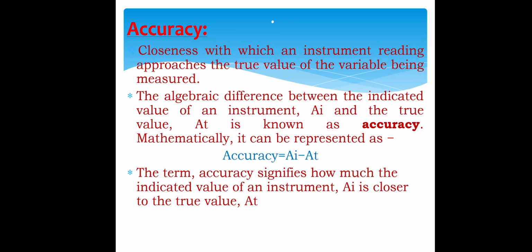So for temperature measurement, it should give the perfect temperature. At a known room temperature of 26 degrees centigrade, we have to get very near to 26 degrees, very close values. So this is known as accuracy. Mathematically, it is the difference between the indicated value of the instrument and the true value of the instrument. Indicated value minus true value will give the accuracy.